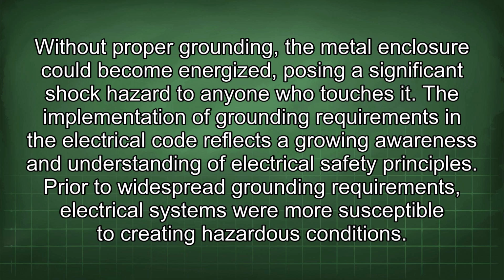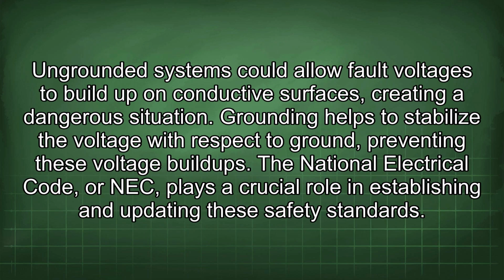The implementation of grounding requirements in the electrical code reflects a growing awareness and understanding of electrical safety principles. Prior to widespread grounding requirements, electrical systems were more susceptible to creating hazardous conditions. Ungrounded systems could allow fault voltages to build up on conductive surfaces, creating a dangerous situation. Grounding helps to stabilize the voltage with respect to ground, preventing these voltage buildups.